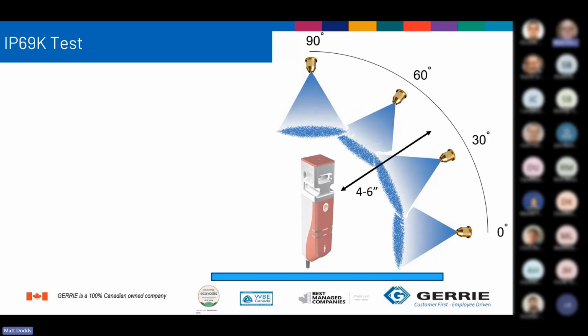So in a recent application, a customer was having issues with tongue-style actuator switches. It was a washdown application, but it really begs the question, what does IP69K mean? So an IP69K has a spray duration. The total test is 2 minutes, where they apply a high-pressure spray at 4 angles, 0, 30, 60, and 90. Duration at each angle, 30 seconds.